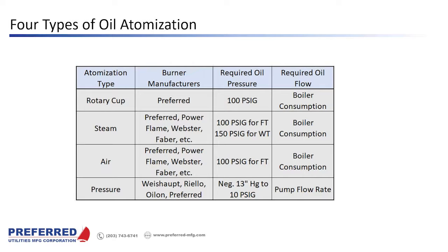So here's a chart. This is the most important slide of this presentation. This tells you the required oil pressure and the required oil flow for the different types of atomization. So if you're going to screenshot anything from this presentation, this is the slide.